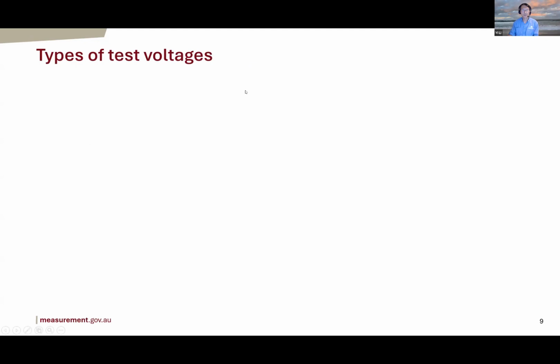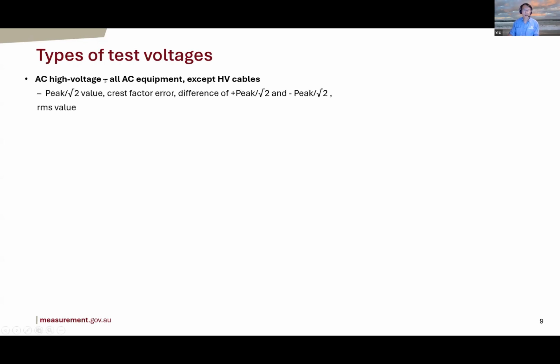Now let's have a look at what type of high voltages are used in the testing. So first of all, AC. AC tests are for all AC equipment, no exception, except HV cables. There are reasons for that. But the value you use to test is peak over root 2, not RMS. The measurement needs to measure peak over root 2 and a number of factors called crest factor error, which is the difference between peak over root 2 and RMS. And also you need to know the difference between the positive and negative peak, because in the actual voltage testing, the insulation responds to peak, not RMS, in most cases. That's why. And DC is used for power cable and DC equipment. DC equipment is becoming more and more prevalent in the network. So what you measure is the mean value and ripple factor.